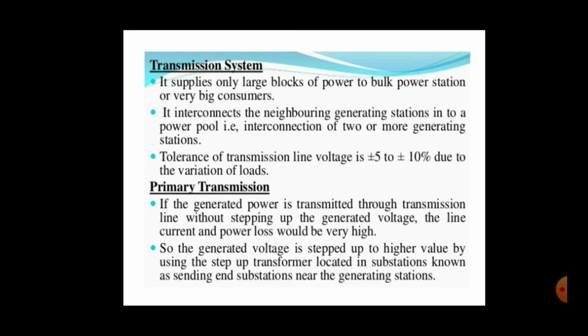Next, transmission system. It supplies only large blocks of power to bulk power stations or very big consumers. It interconnects the neighboring generating stations into a power pool, that is, interconnection of two or more generating stations. Tolerance of transmission line voltage is plus or minus 5 to plus or minus 10% due to the variation of loads. Next, primary transmission. If the generated power is transmitted through a transmission line without stepping up the generated voltage, the line current and power losses would be very high.